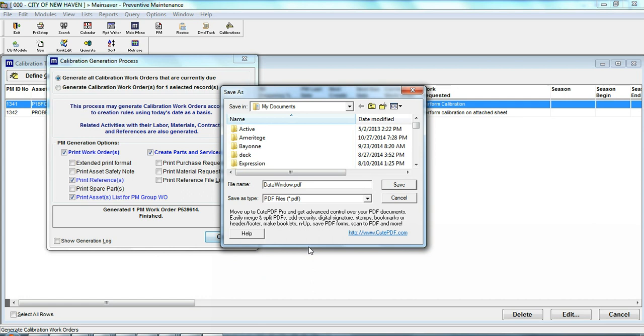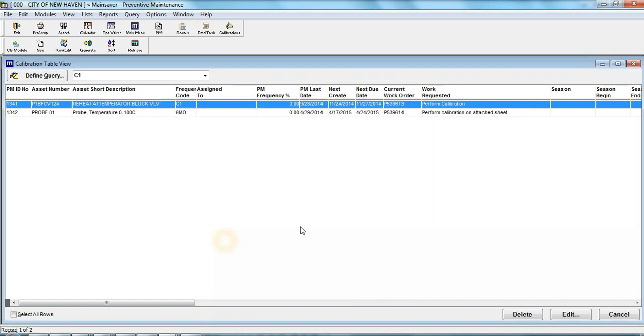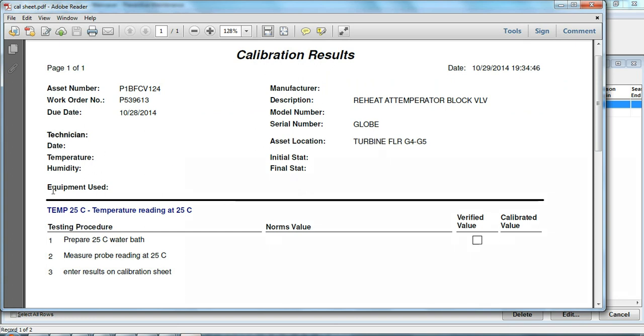Now I have a calibration sheet all set up, so I'll just show what that looks like. This is just one with a 25 degrees C temperature reading, and it shows you what you want to do, and if you had a norm value in there, it would print it out. But this is where you put the verified value, what you found, and then if you do the calibration, this is where you would record how you left it if you had to adjust anything.